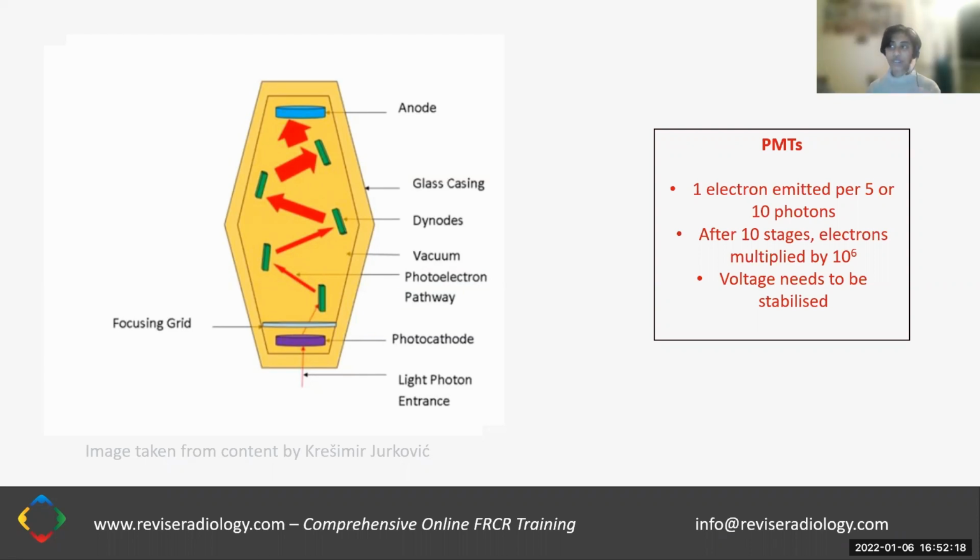What's happening here is that a photon from the patient's body has gone on a journey. It's become visible light. It's become a lot of electrons. Those electrons are picked up and turned into an image on the screen. And the tube is constructed so that although only a few of the gamma photons are picked up, we can minimize the dose while also getting a really legible image.